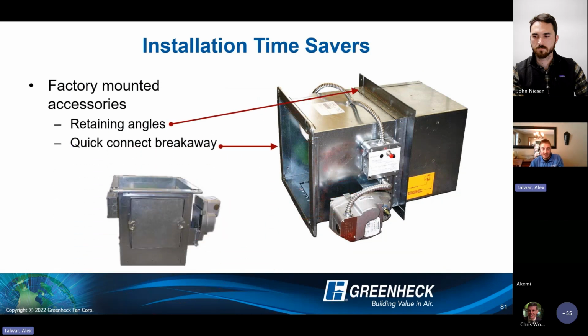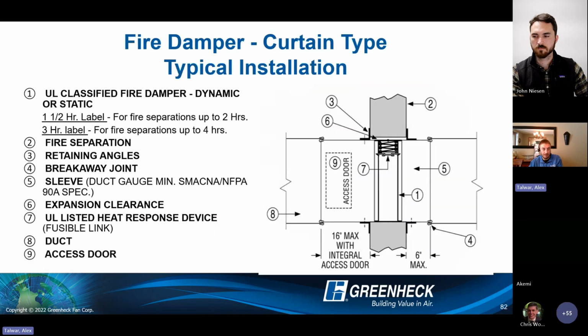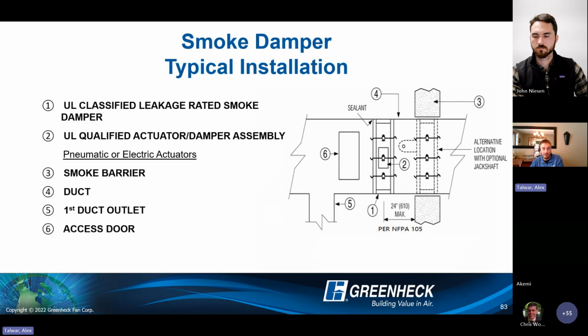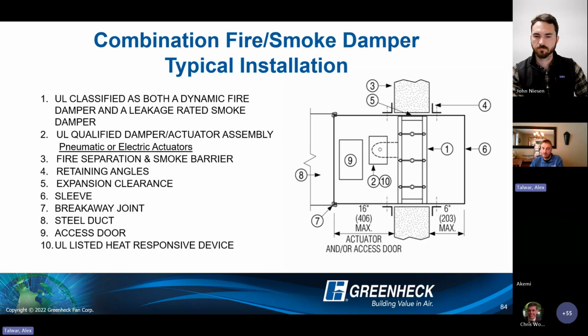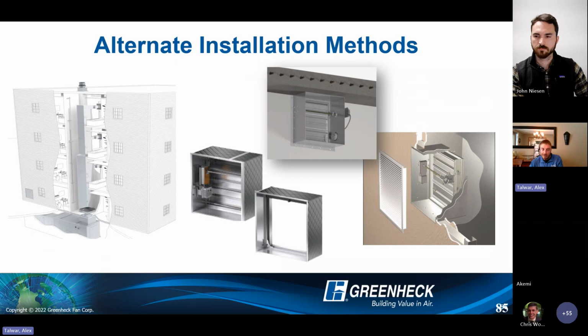Of course, accessories we're always able to provide factory mounted to help save time in the field. These are some good reference slides I like including just to show all the different things to be aware of about the installation. Again, I don't quite have time to go into it all. Smoke dampers, you've got a little more leeway than the fire rated products. You can actually slide them right into ductwork as long as you're within 24 inches of the smoke barrier. Still need the access, of course, and the combination product here. Let's start wrapping it up.